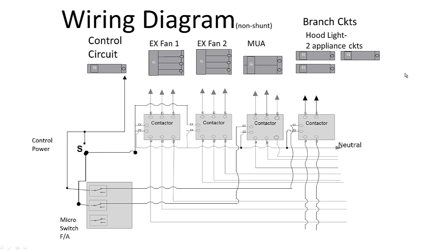Here's what we've got. I have the individual circuits — two appliance circuits under the hood and one for the hood lights. We've got a two-pole breaker for the make-up air, contained on this third contactor. That covers the lighting as well as the make-up air, our three-phase exhaust fans, and our control circuit. The contactor for the appliance circuits underneath the hood — the fryers and the cooktop — they're on constantly.